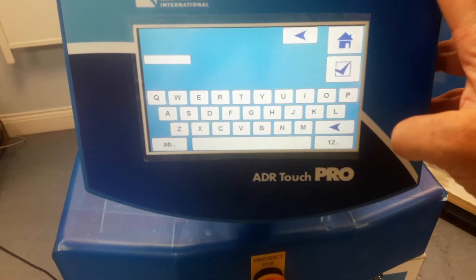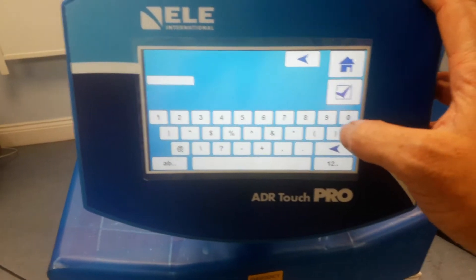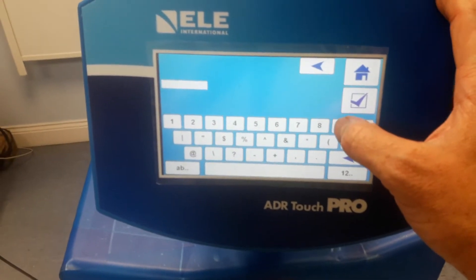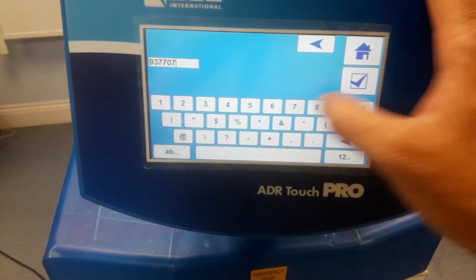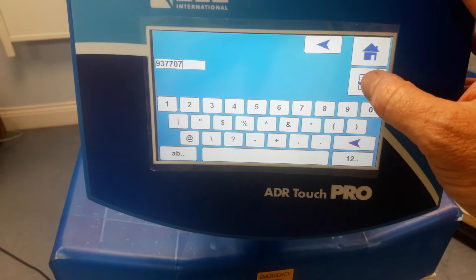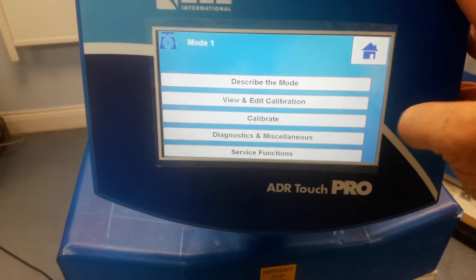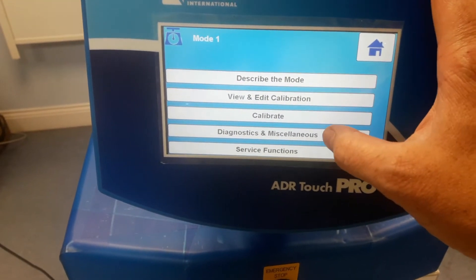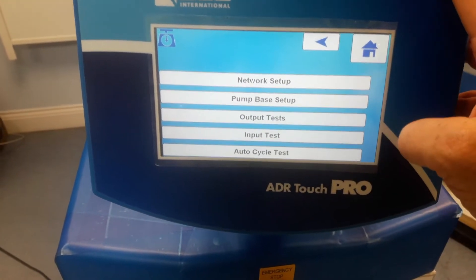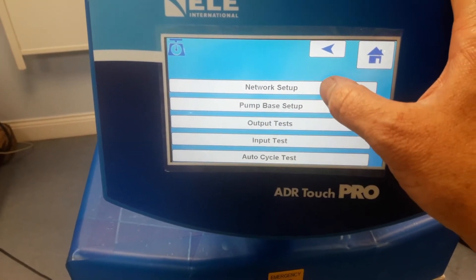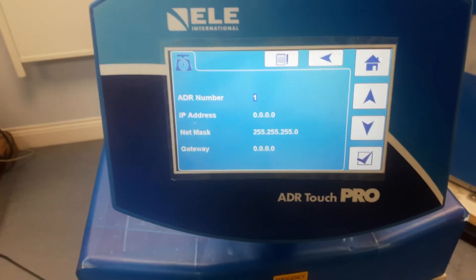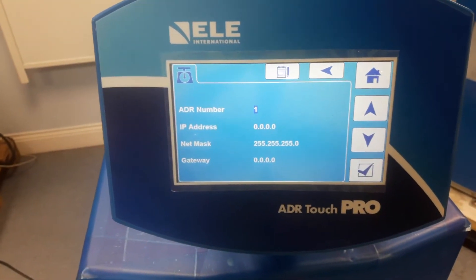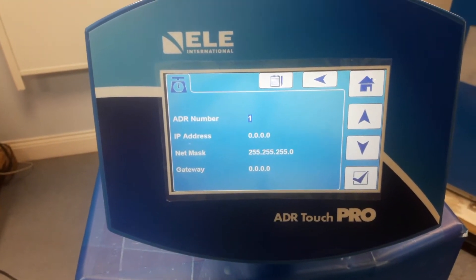This is done with the code 9-3-7-7-0-7. Press Enter. We're going to select Diagnostics and Miscellaneous, and then Network Setup. You can see in here there are various fields which can be set and adjusted.